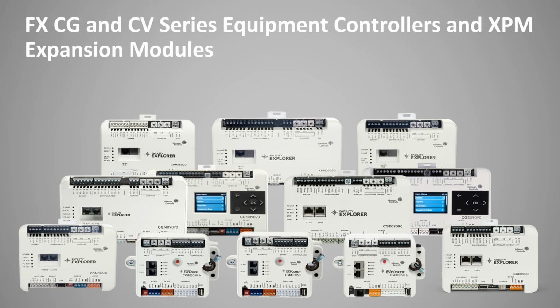Now inside of CCT, Johnson limits their addressing for BACnet from 4 to 127, okay? Because Johnson uses address 1, address 2, address 3 as other devices in the field. We'll get into that later, but there are some devices you can use to plug into these and program them in the field, and they actually are master devices in the field. They actually have a MAC address. So that's why Johnson inside of CCT limits that from 4 to 127.